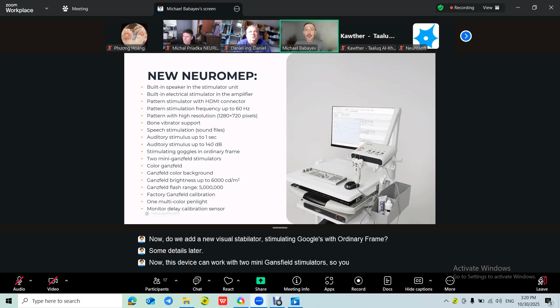And we add a new visual stimulator, stimulating goggles with an ordinary frame. Some details later. Now this device can work with two mini Ganzfeld stimulators, so you can stimulate both eyes of the patient at the same time. And Ganzfeld is now color. Ganzfeld flash color can be, and background can also be, any color as you like. The previous one had only a white flash. And we increase Ganzfeld brightness up to 6,000 candelas per square meter. So with this brightness, it's possible to make all standard ERG techniques. And Ganzfeld flash range now is 5 million. It includes not only the stimulus intensity change, but also the change of the duration of the stimulus.